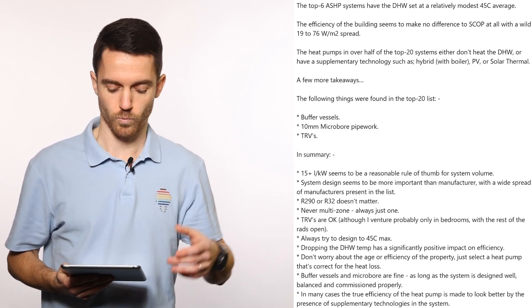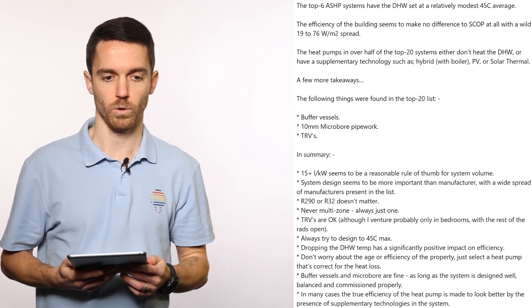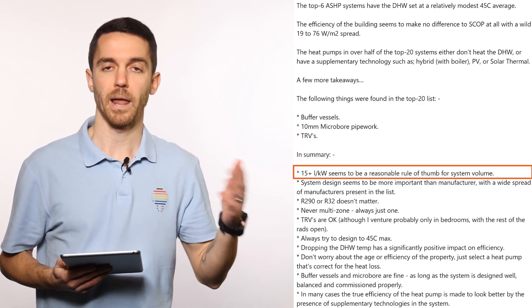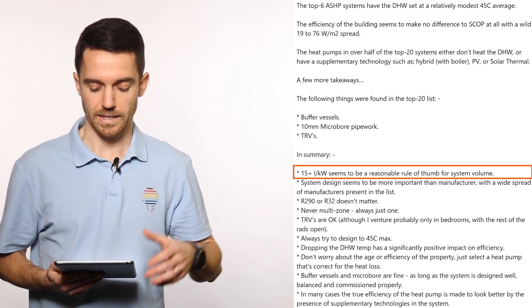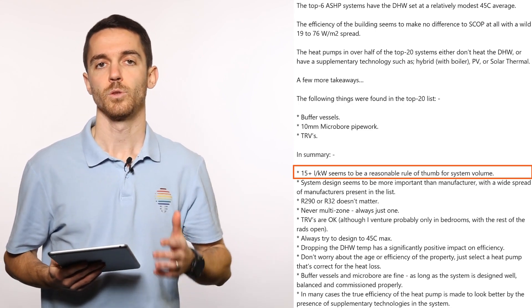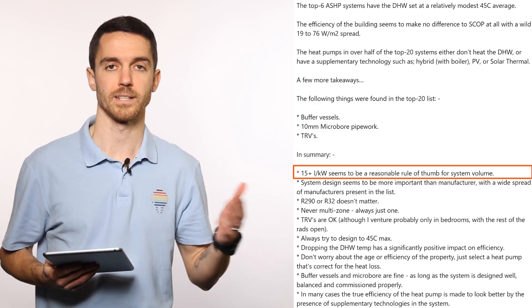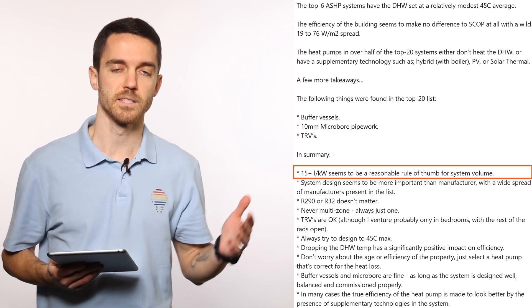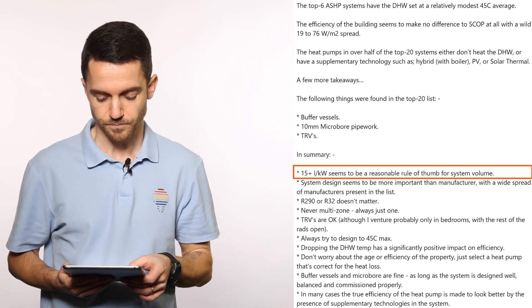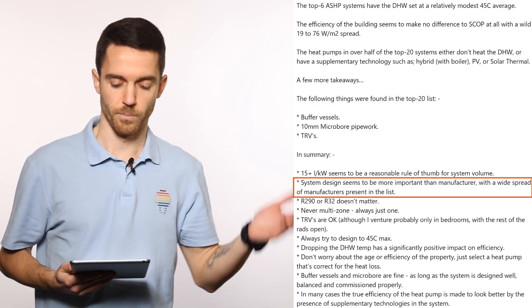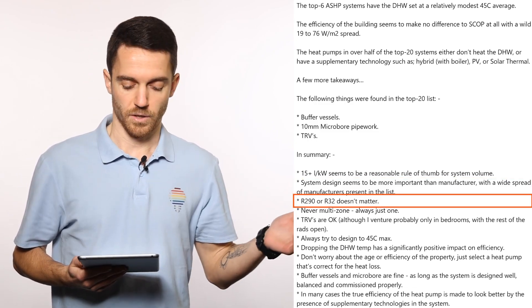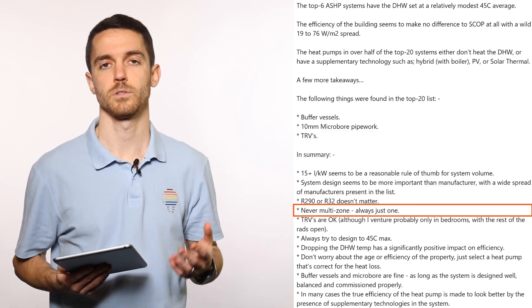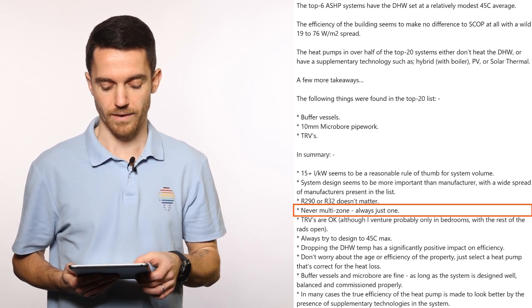In summary, what you need to know and what will impact your performance: first, 15-plus liters per kilowatt is the rule of thumb for system volume — so 15 to 20 liters per kilowatt. For example, if you have a 5 kilowatt unit, that's 75 to 100 liters — best for modulation and performance. System design is more important than manufacturer. Refrigerant doesn't matter. And one single zone will always outperform multi-zones.